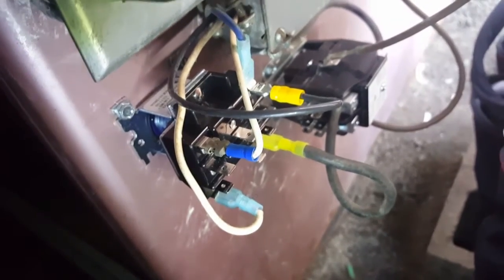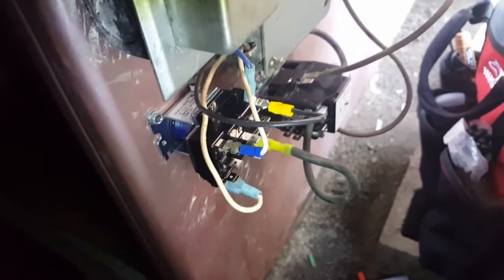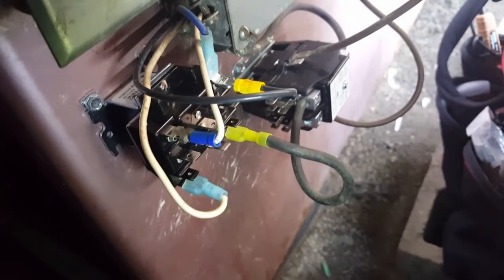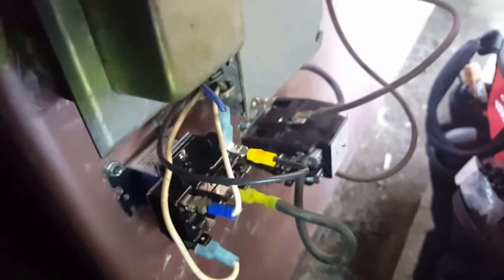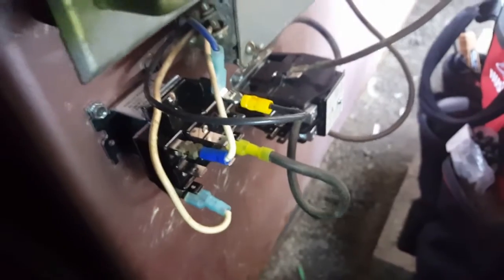We have power that passes from another 120 volt leg onto the fan motor to power up the fan in cooling mode. So this allows the fan to run in cooling mode even when there's no call from the fan and limit switch in the oil furnace. And that's all it is. But it probably can be simplified a little bit. I just replaced the components they had in place. It's been around for about 25 years now, so this should get them through the finish line.